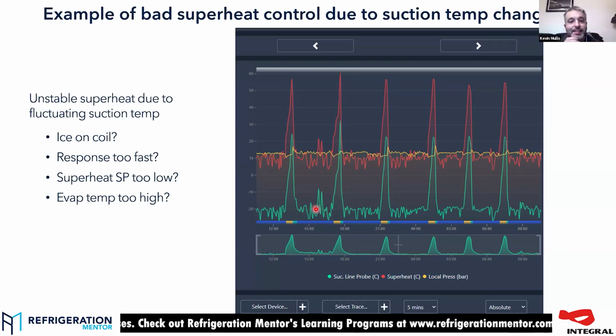And there's a range of things it can be. Ice, as we just discussed, is quite a common one. A little bit of ice, a lot of ice. If you've got weird superheat control like that and everything looks okay in the settings, nobody's gone crazy, you need to physically check the coil. I've been told 100 times there's no ice on the coil, only for somebody to go up, switch the fan off and find ice on the coil. So it's a really important one to check.